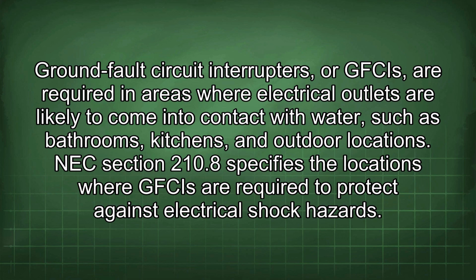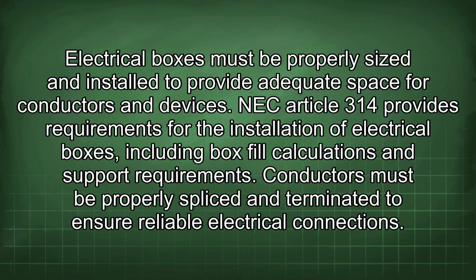Ground fault circuit interrupters, or GFCIs, are required in areas where electrical outlets are likely to come into contact with water, such as bathrooms, kitchens, and outdoor locations. NEC Section 210.8 specifies the locations where GFCIs are required to protect against electrical shock hazards. Electrical boxes must be properly sized and installed to provide adequate space for conductors and devices. NEC Article 314 provides requirements for the installation of electrical boxes, including box fill calculations and support requirements.